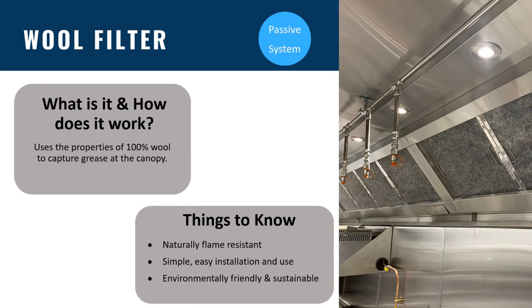Wool filters. Well, there's a growing interest in wool filters due to their simplicity and their green credentials. They also protect and offer extended life and efficiency to expensive odour control systems such as activated carbon. So how does it work? Well, these are alternative stainless steel baffle filters that are used in the canopy in conjunction with 100% wool pads. Data sheets on them claim up to 98% grease capture. The process? Well, greasy vapours are drawn through the wool filters, whereby the grease particles naturally adhere to the wool fibres upon contact. The captured contaminants are stored along the wool fibres. This prevents blocking and is why airflow reduction is negligible. As the wool fibres approach their capacity, small droplets of grease begin to form on the outer face fibres of the wool filter. These droplets are the visual indication that the filter needs changing.